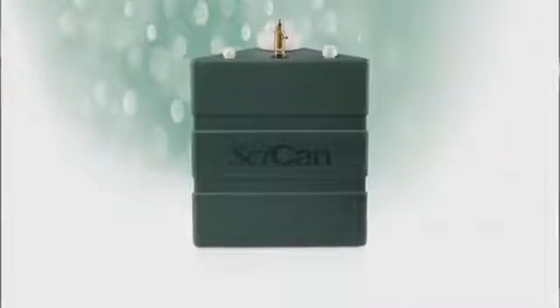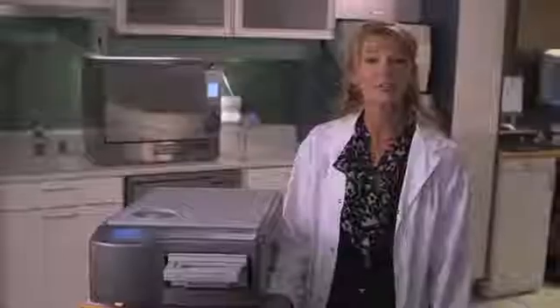Another optional new feature is the StatFlow waste bottle. Because all Statims use fresh, steam-distilled water on each cycle for gentler sterilization and better performance, the new StatFlow waste bottle is a plumbed, permanent, under-the-sink option to handle all waste water. Imagine — no cleaning or dumping of the waste water bottle, ever.